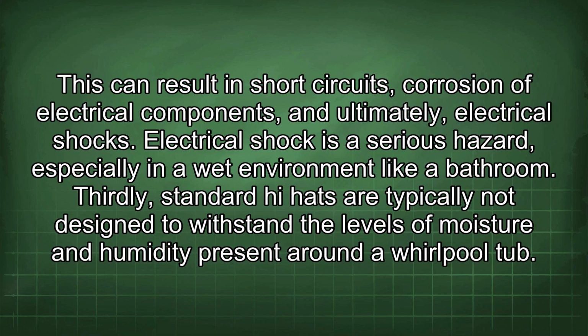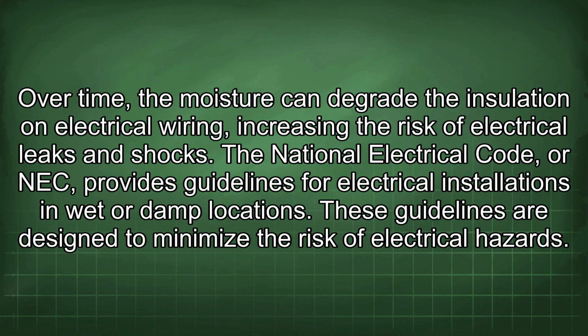Thirdly, standard hi-hats are typically not designed to withstand the levels of moisture and humidity present around a Whirlpool tub. Over time, the moisture can degrade the insulation on electrical wiring, increasing the risk of electrical leaks and shocks.